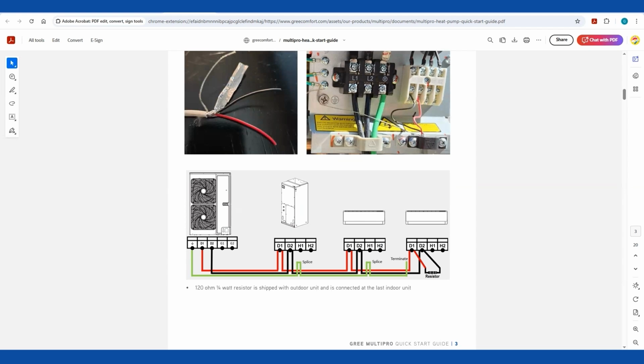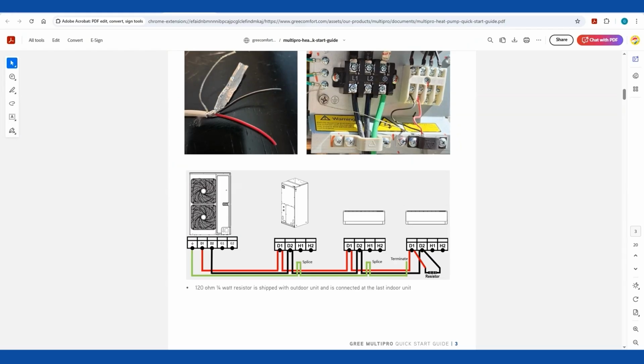And I tell guys all the time, you got two different cables here, the actual cable. Take them ground wires and just twist them together and lay them back on the cable and wrap them up with electrical tape. You do that, you've got a solid enough connection. You don't even need to use a wire nut. And we ensure that that ground's not touching anything on the indoor units. We do not want that ground touching anywhere. But you got to carry it through. So if this is your first unit, you need to splice here, splice at your second unit, terminate at the last unit. Really all you want to do is cut that off and just make sure it can't touch anything.